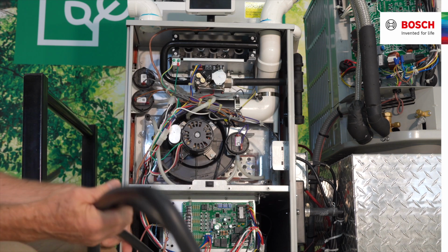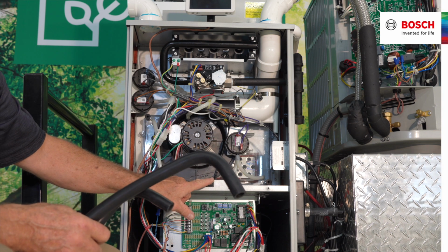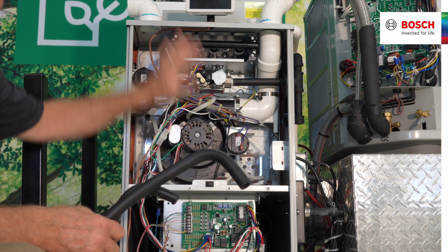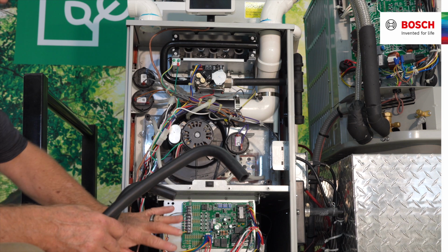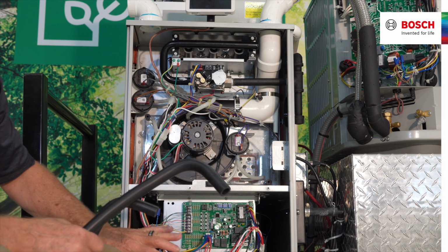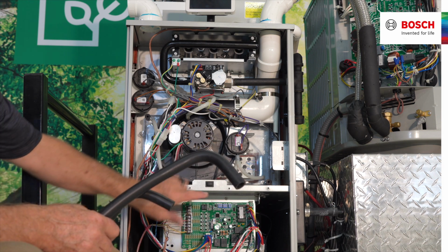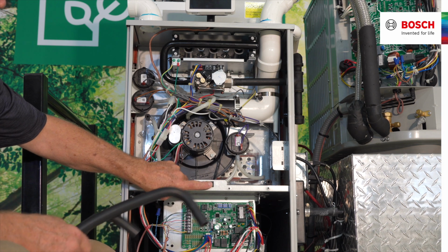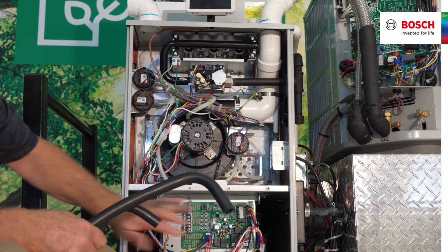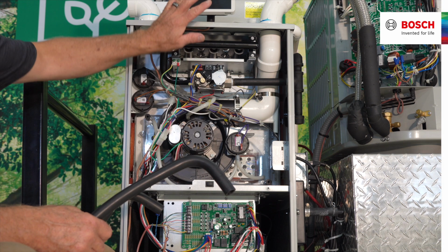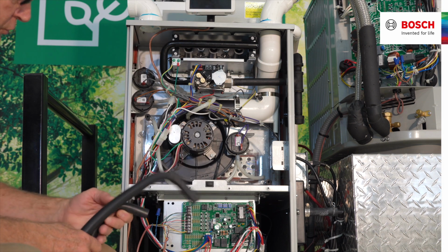Remember that the door switch is an L1 type safety device. So this furnace is not going to light up, it's not going to come on, it's not going to produce the 24 volts or low voltage without that door switch being engaged, powering up the transformer, powering up the board, and of course powering up the controller.